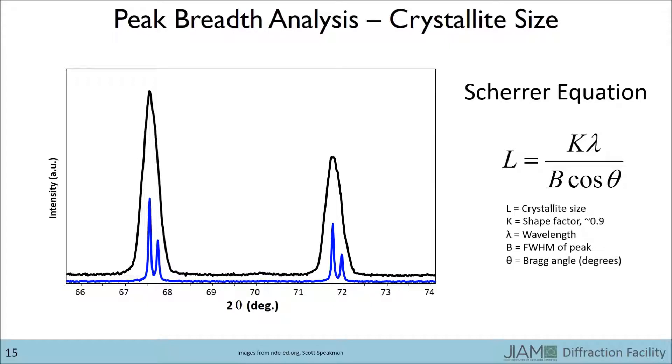For instance, based off of what I have told you so far, you would think that the sample that produced the black curve should have a much smaller crystallite size than the sample that produced the blue curve. Surprisingly, both patterns were made with the same sample. The difference is that different diffractometers and optics were used. This illustrates the fact that there is some inherent instrumental broadening of the data you collect related to the incident and diffracted beam optics that must be accounted for before further analysis.